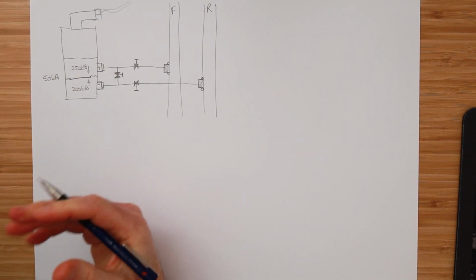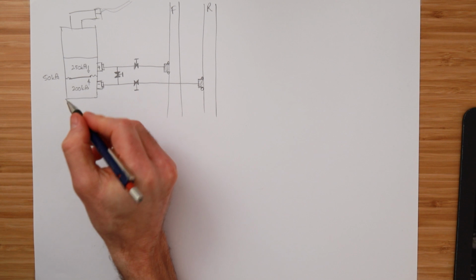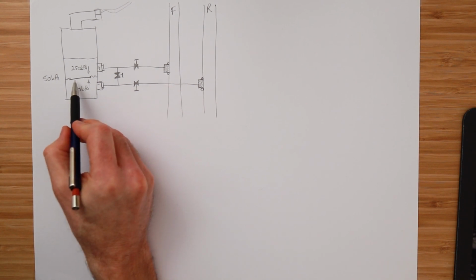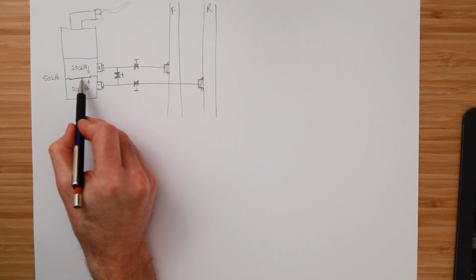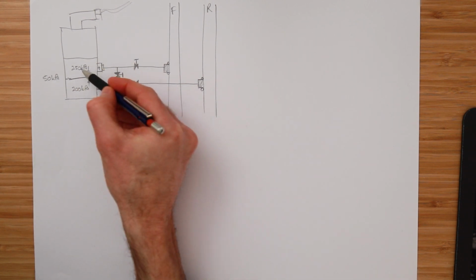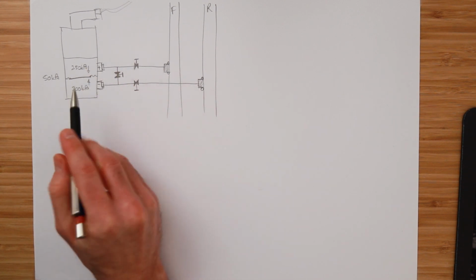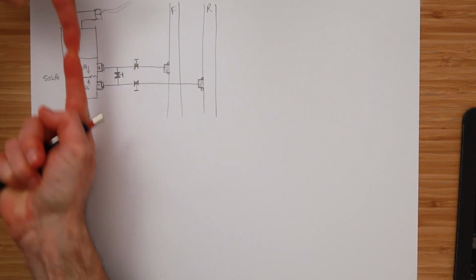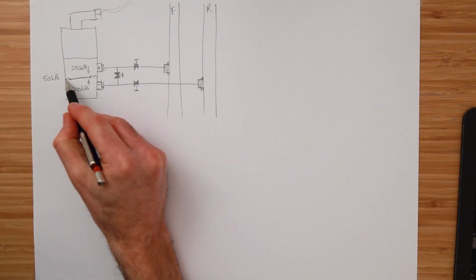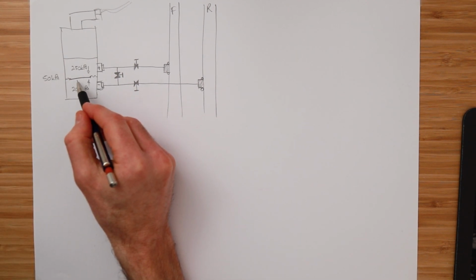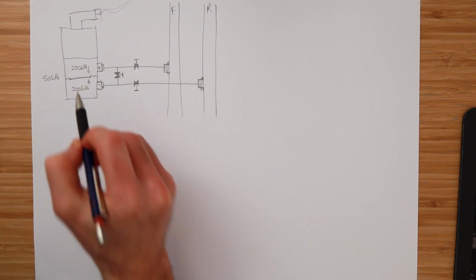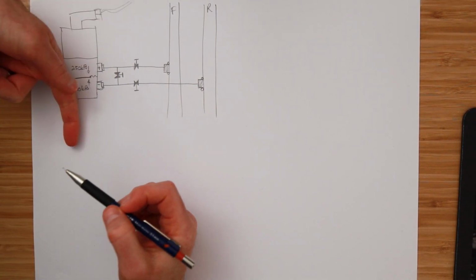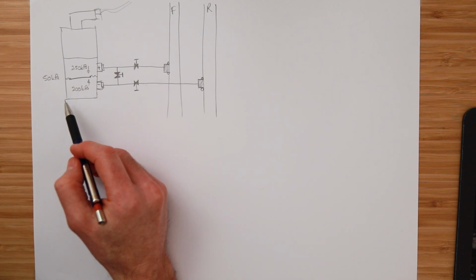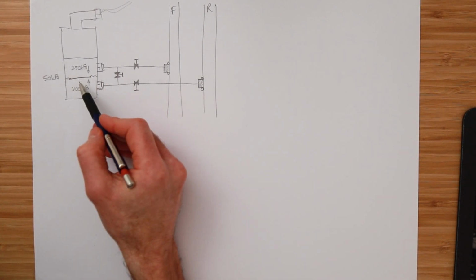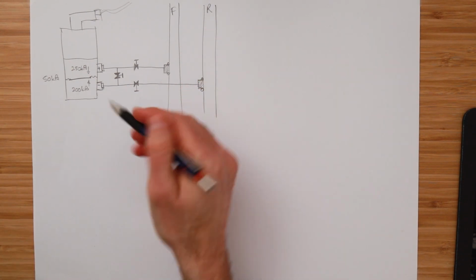And that's how the differential pressure transmitter works. What's very important to understand here is that, in my opinion, the diaphragm can withstand a reasonable amount of pressure as long as that pressure is equal on both sides. It's equally pressing on the diaphragm, the same amount of pressure. This diaphragm cannot withstand a lot of pressure on one side, but not the other side, because the pressure just bursts the diaphragm out.